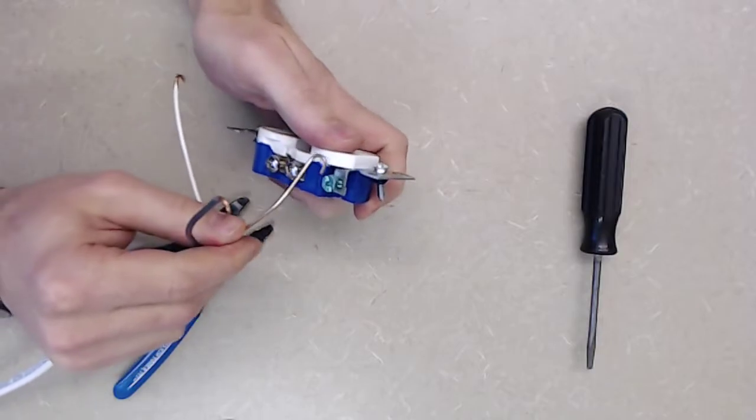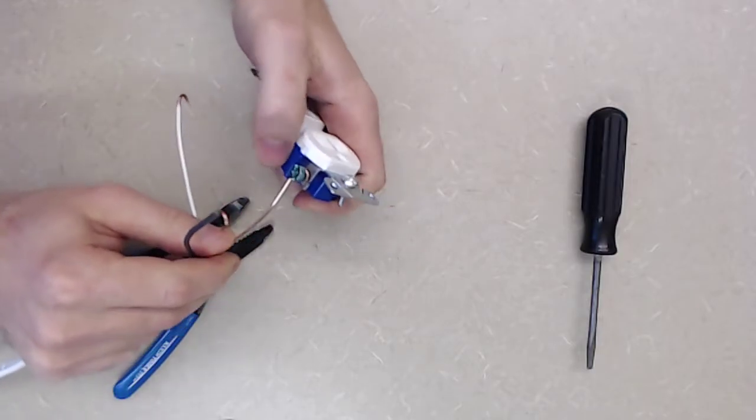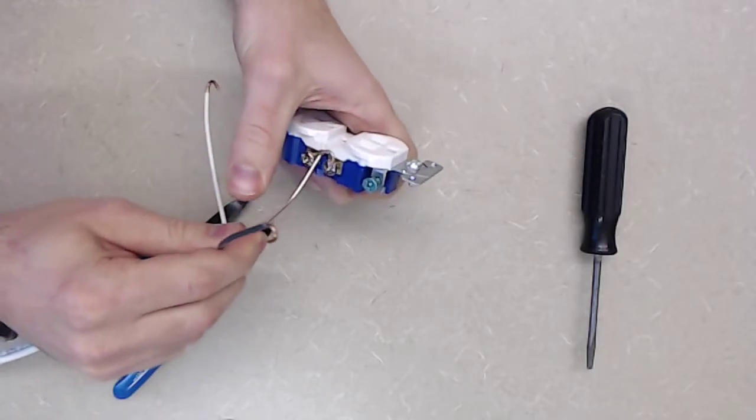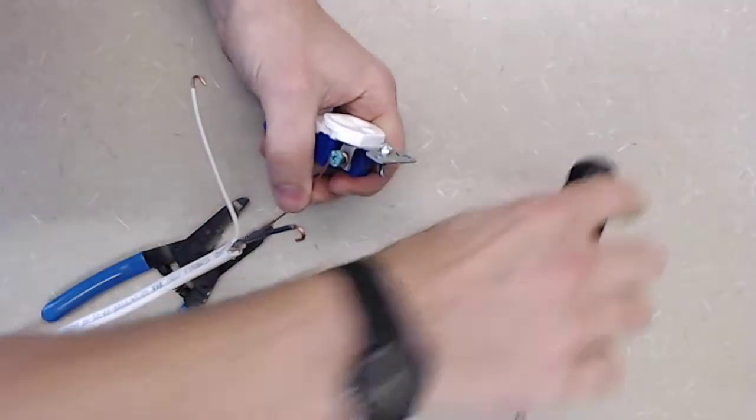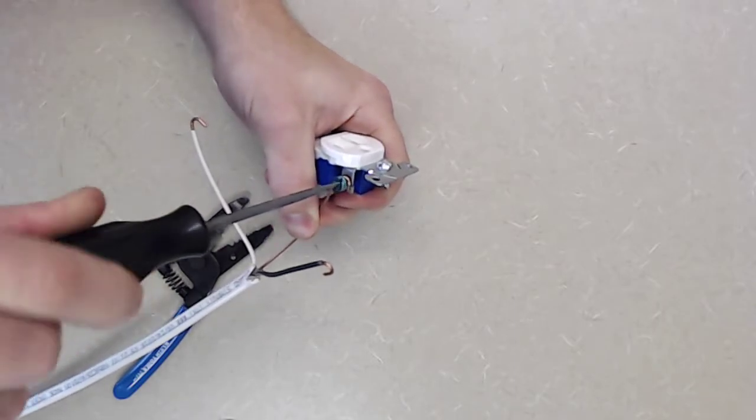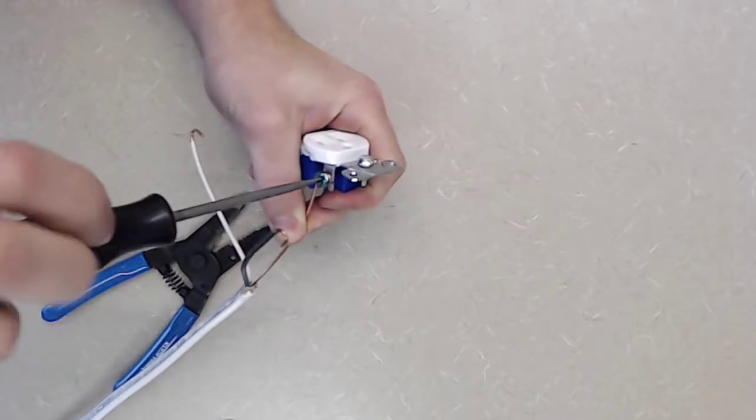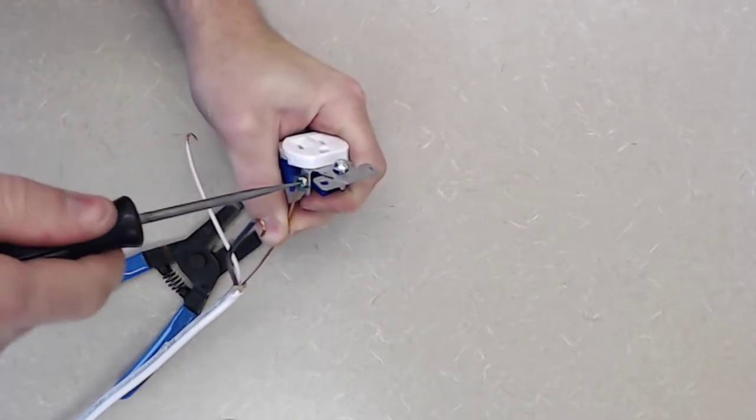So starting with the ground coming in here, and I always want to wrap that wire clockwise around the screw, because that's the way that when you tighten it, it's going to actually pull that loop of the conductor into itself.